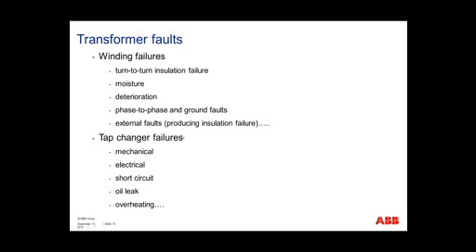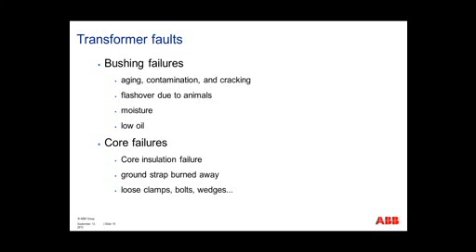A source of faults could be the tap changer. The tap changer is a mechanical device and electrical device, so there is some coupling there that could fail. You could have short circuit failure of the tap changer, oil leaks, overheating.